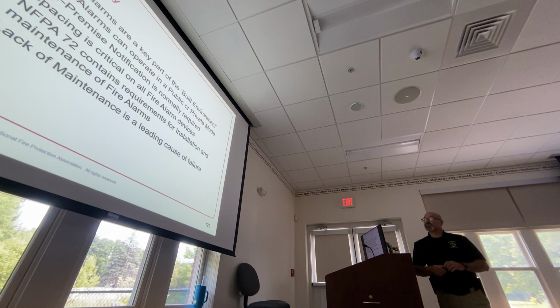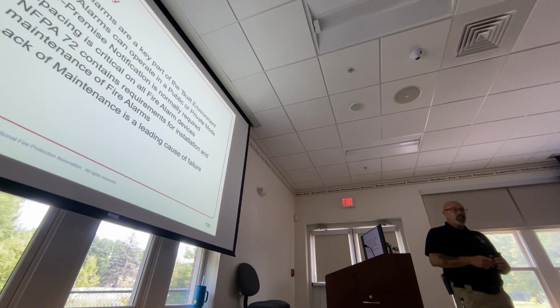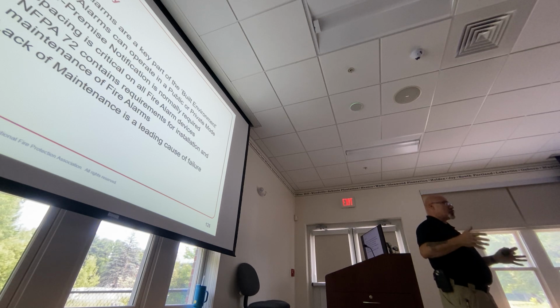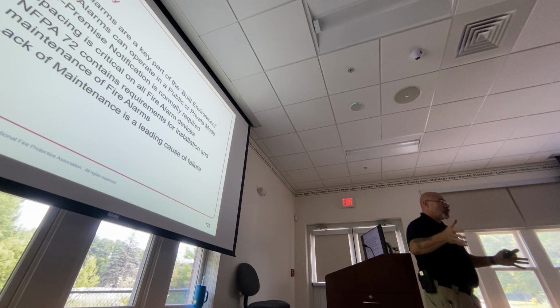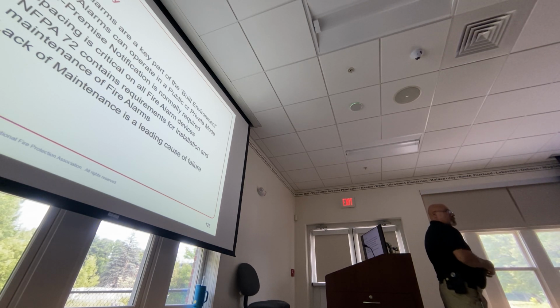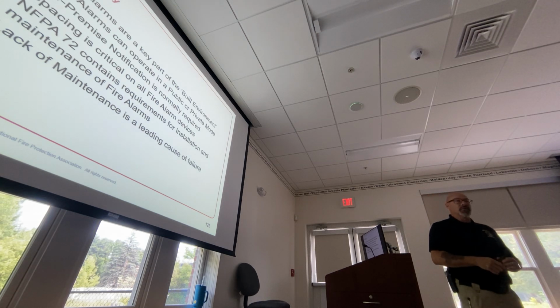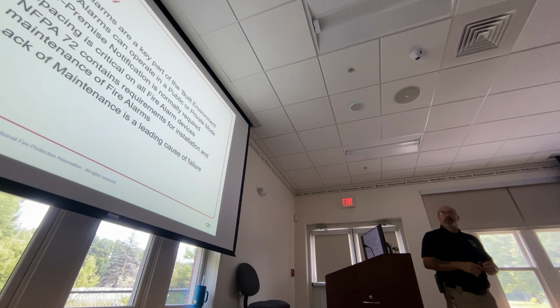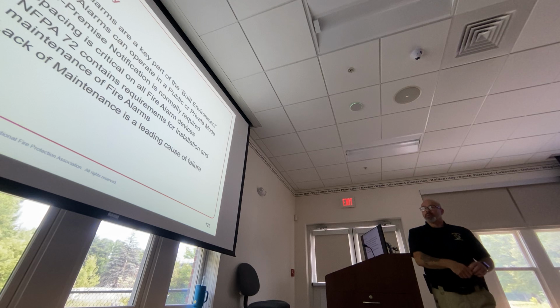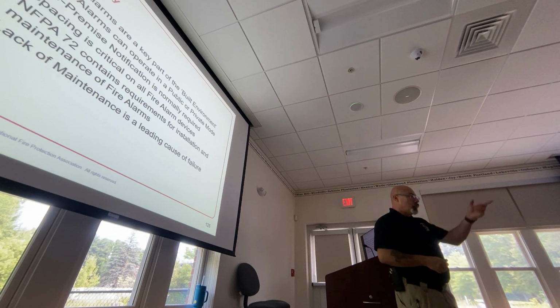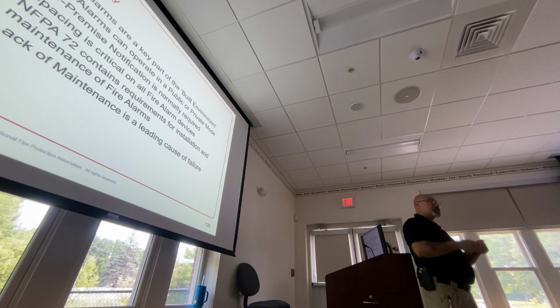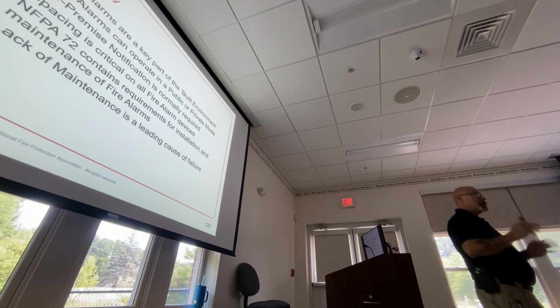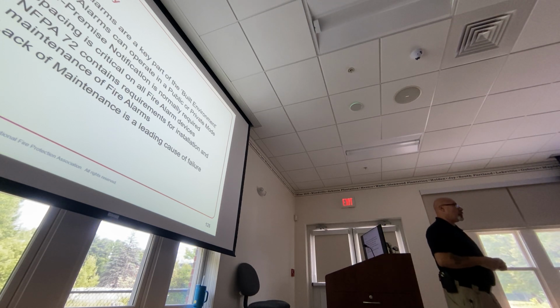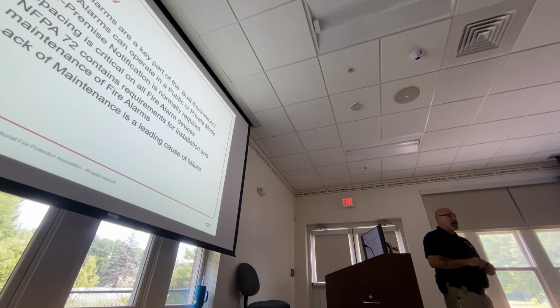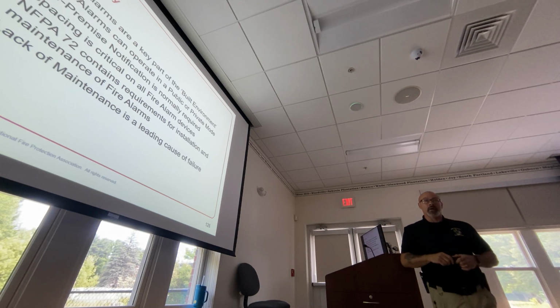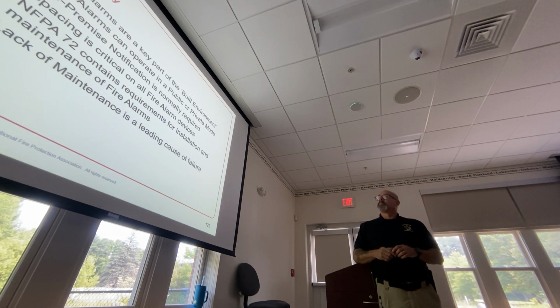Off-premise notification is normally required. In most occupancies, it's not just going to ring locally. It's going to ring locally and call a central station or a supervising station. It's going to notify a fire department. Portland calls, it notifies the fire department. Their system is all integrated. I believe everything calls the fire department in Portland, if I'm not mistaken. Waterville used to be that way. I think they're getting away from that.